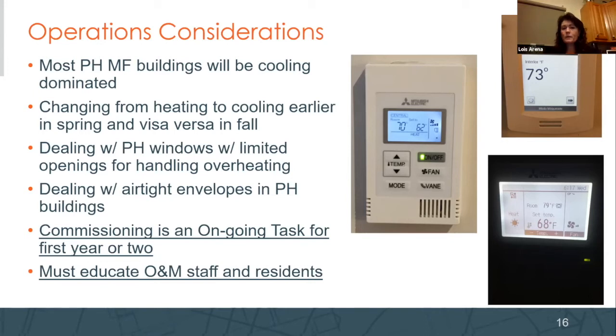Passive house windows in multifamily buildings have limited opening profiles. So even if you say, well, it's very valid to open your window and cool off your home, it is. But if you only have a 2-inch or 4-inch opening and an awning, you're not getting a lot of cooling from that outdoor air, no matter how cold it is outside. So you have to keep that in consideration. Dealing with airtight envelopes, we just don't lose heat to the outdoor elements as we do, so the internal gains dominate.